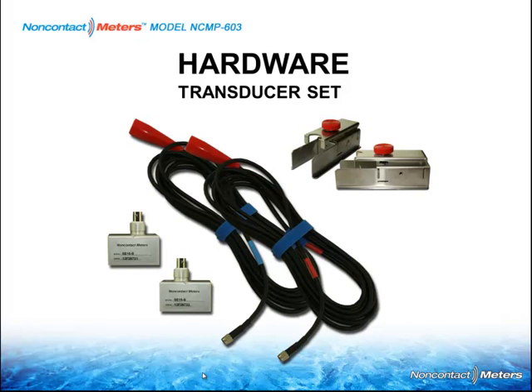Moving on to the hardware of the transducer itself. The transducers come as a pair, and in this case they are 1.2 megahertz. Again, transducers with each brand of transit-time flow meter are unique, so they're not interchangeable. They have different frequencies and different angles, so you have to buy them as a pair because they're matched. These are good for 1 to 48 inches, same set, and they're perfect for any rigid plastic or metal pipe. It does not work well with flexible hoses because their shape is nondescript, so the math is not there to do something that's not perfectly round.